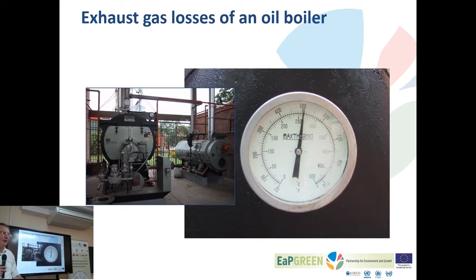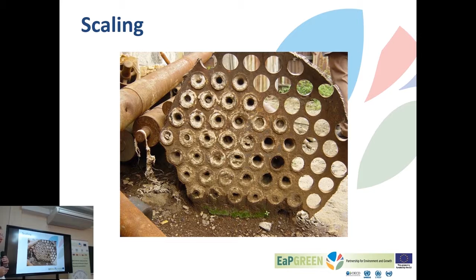Now, a difference of 130 degrees means 6-7% less fuel for the same benefit. How do you like this picture? Showing a heat exchanger, showing some scaling, some deposits. How long does it take until a heat exchanger has deposits like that, even allowing very hard water? Apparently, maintenance people had not looked into their equipment for months or years. So good maintenance is a really important issue also in a dairy, because this of course is not true for dairies only. This is true now for any industry.